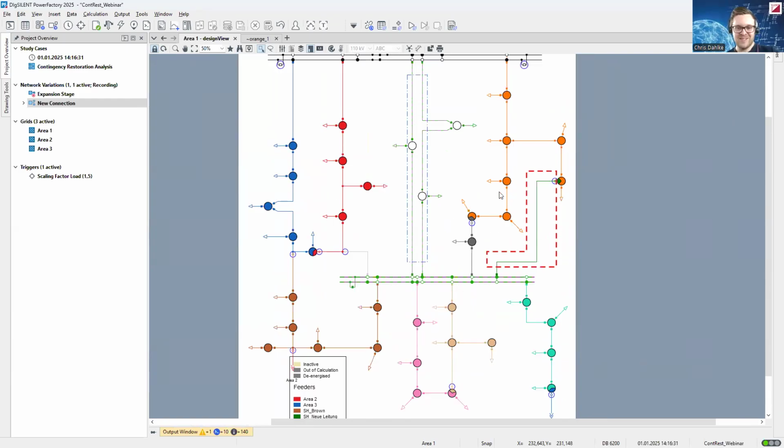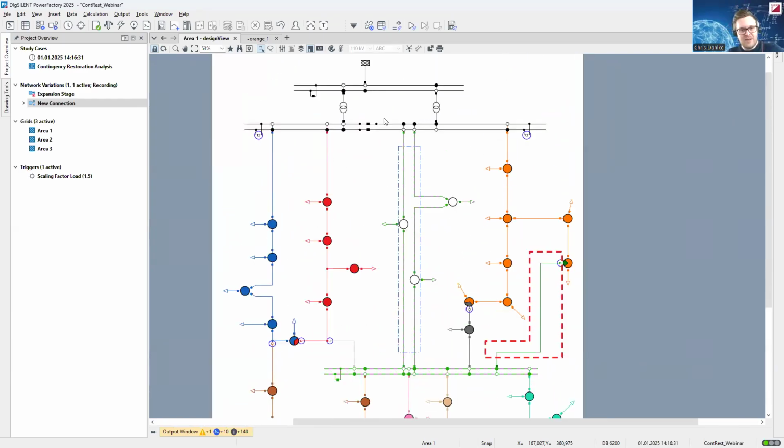So this means when you have modeled several stations here, when I not only have this one, but another one as well, then the backward recovery would be a possibility if, for example, the contingencies here are of these transformers. It may also be the case that maybe only one of them is in service and the other one has an outage. Then normally we would have no way to resupply any customers in this grid.